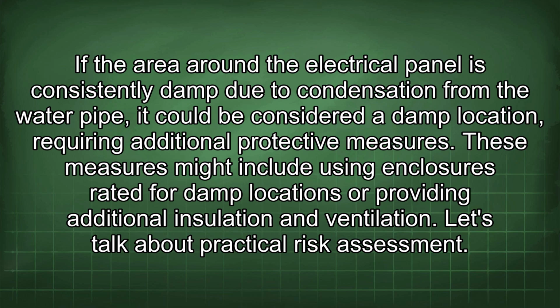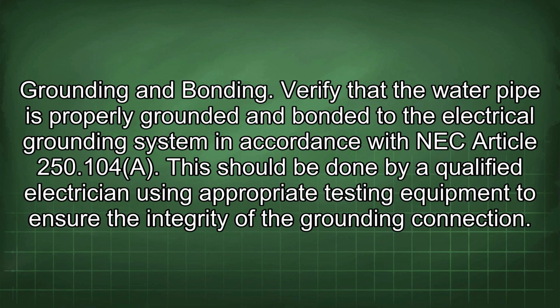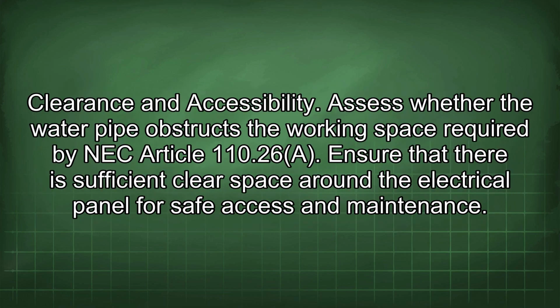Let's talk about practical risk assessment. Grounding and bonding. Verify that the water pipe is properly grounded and bonded to the electrical grounding system in accordance with NEC Article 250.104(A). This should be done by a qualified electrician using appropriate testing equipment to ensure the integrity of the grounding connection. Clearance and accessibility. Assess whether the water pipe obstructs the working space required by NEC Article 110.26(A).